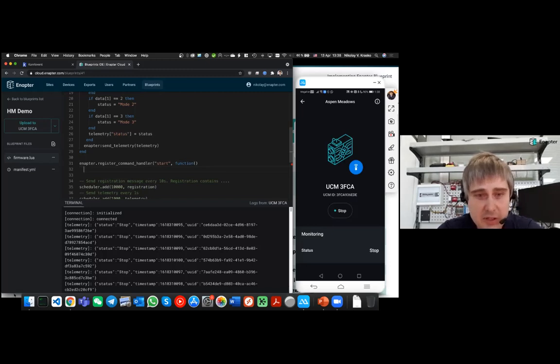For this, we will use the Modbus library and the write holding function. The address of our device is in the address variable. The register we will use is 999, and the value is 1, meaning we start the system. We'll set the timeout to 1 second again.